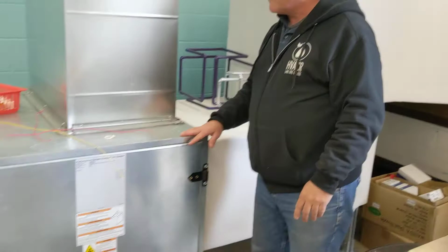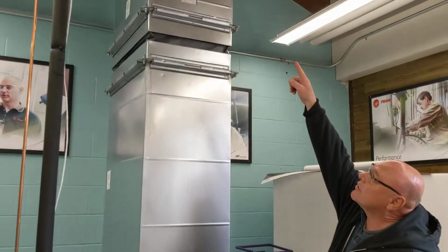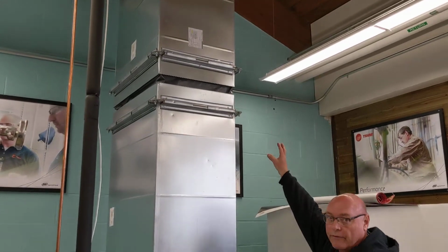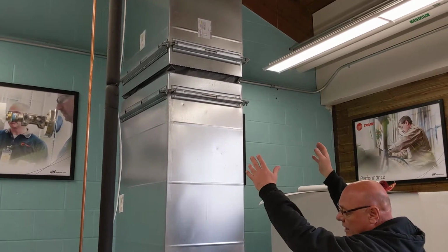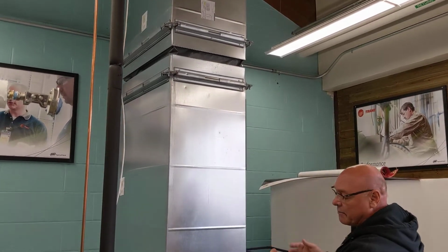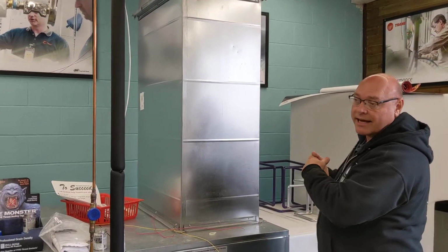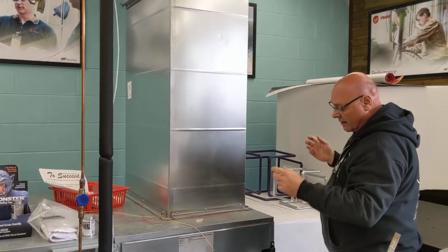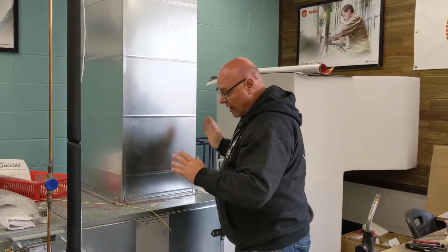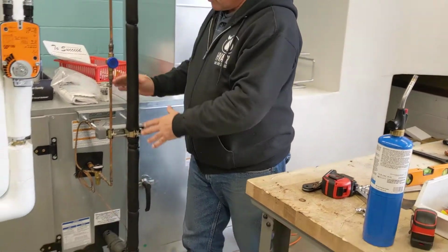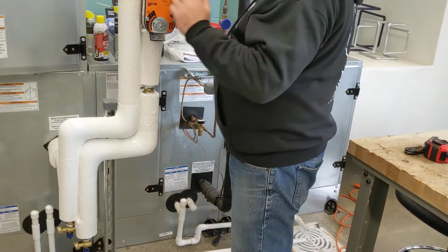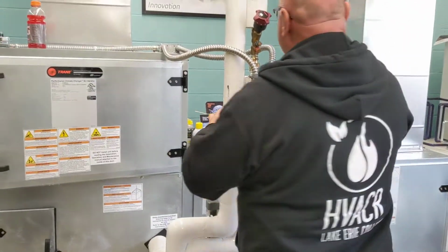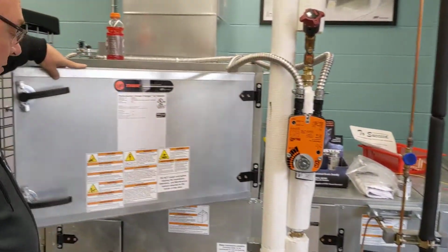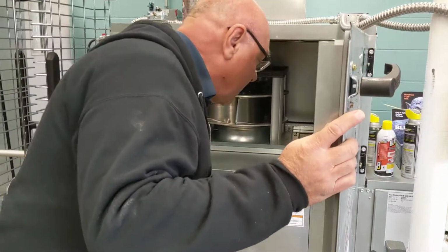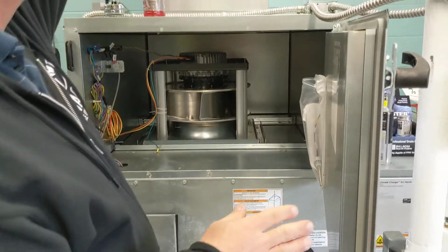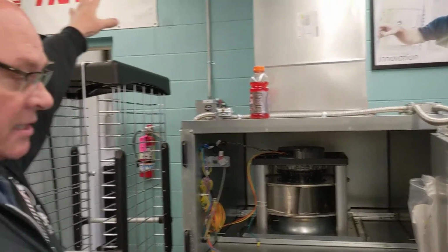Air handler either brings in outside air, which is coming from here, and then goes into a filter rack, or we have return air from another part of the building, and we just bring that air back if we don't need outside air for additional cooling. We have a filter rack here. It goes through.